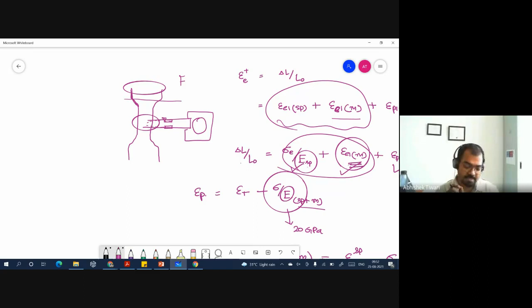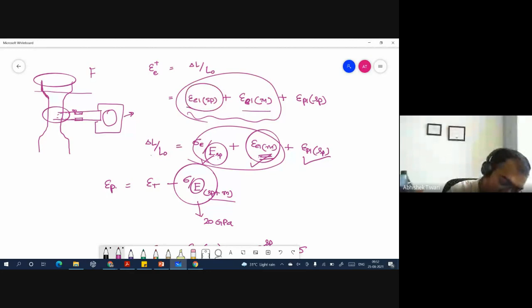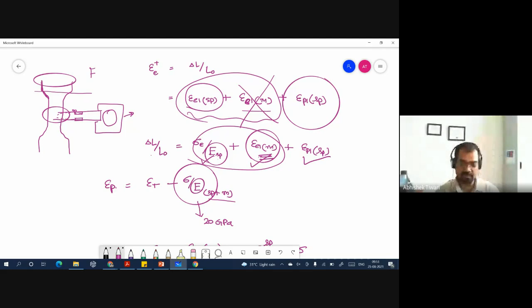So when you do that, you are not measuring anything which is coming because of the machine, right? And by using this instrument, you can calculate directly only the strain which is because of the sample and not because of the machine. But an extensometer usually has limits, because you can't use it every time you do the test, unless you have a lot of money and can destroy an extensometer after every test. So usually what is done is that we remove the extensometer after 2% of the total deformation. Within 2%, usually metallic materials will hit plasticity, and the Young's modulus can be calculated in the elastic region only. So you don't need to have the extensometer data in the plastic part, right?